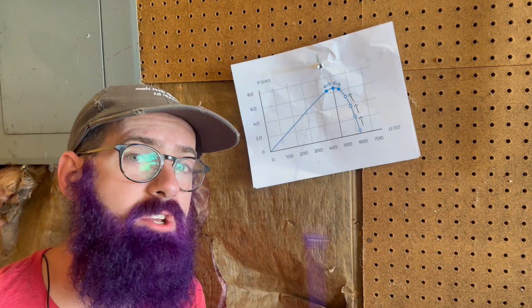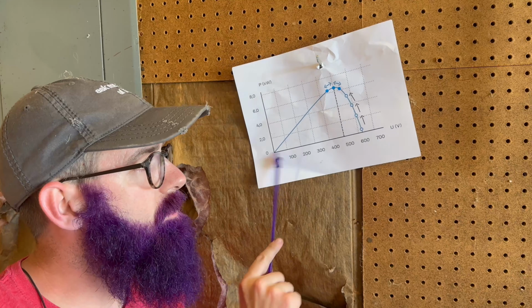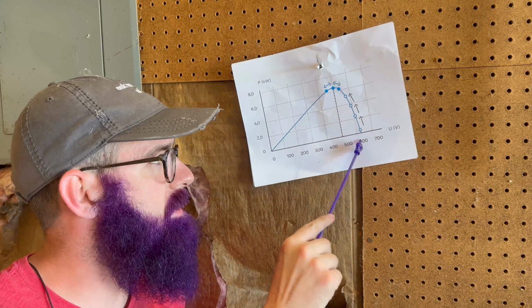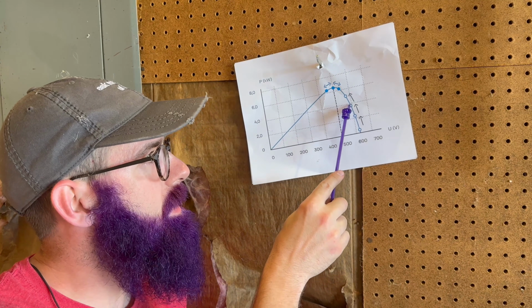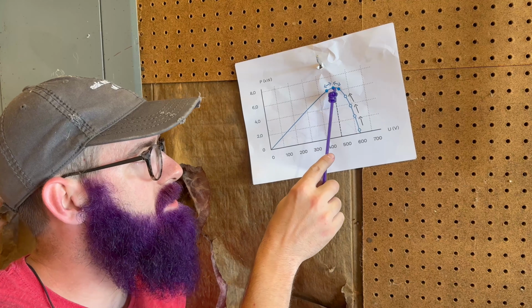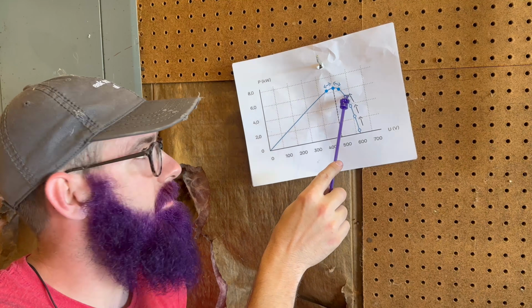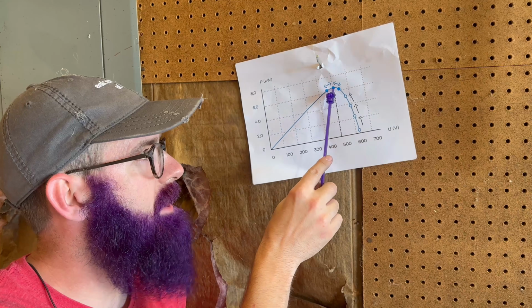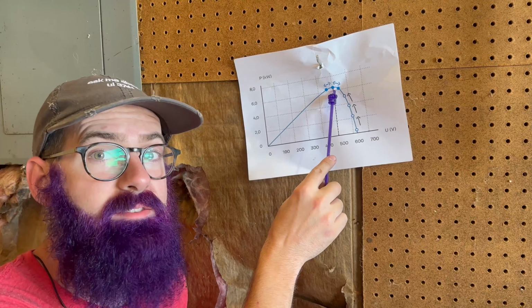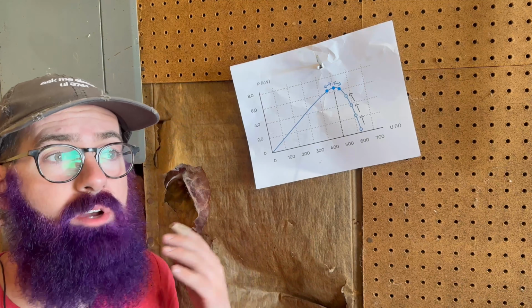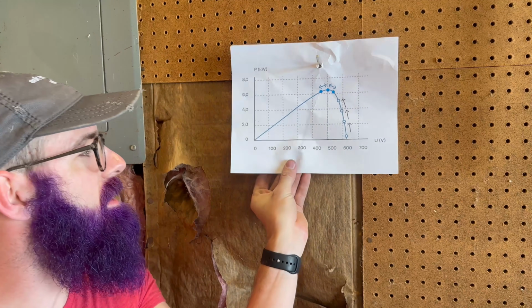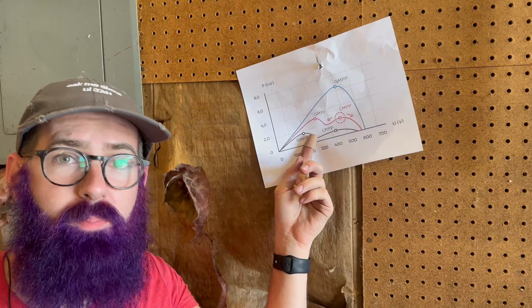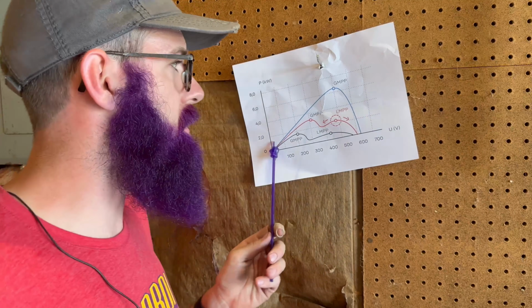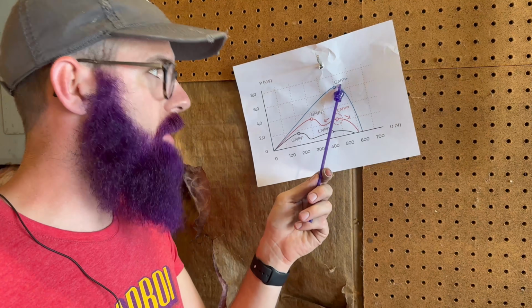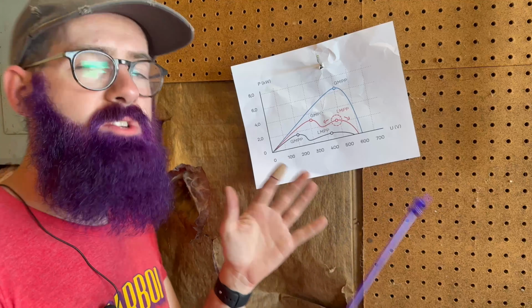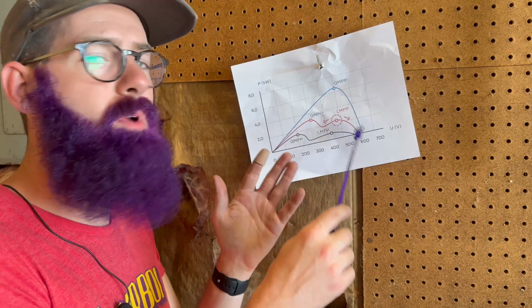How power trackers used to work is that they would go from the highest voltage they could, open circuit voltage. They'd go up and up and up to try to get the highest wattage they could out of this curve. And they'd kind of go back and forth here a little bit until they found, yeah, this is the best voltage. But there's a problem with that when you talk about shade, because shade can really mess up your power curve. So this again is your normal power curve. You've got your global maximum power point right here. And then once you start to have shade, it starts splitting up into multiple humps.